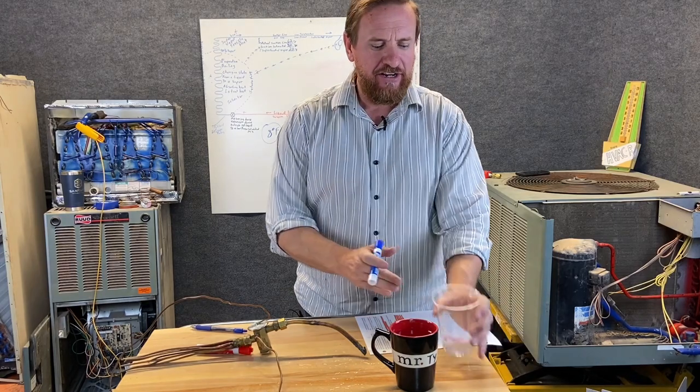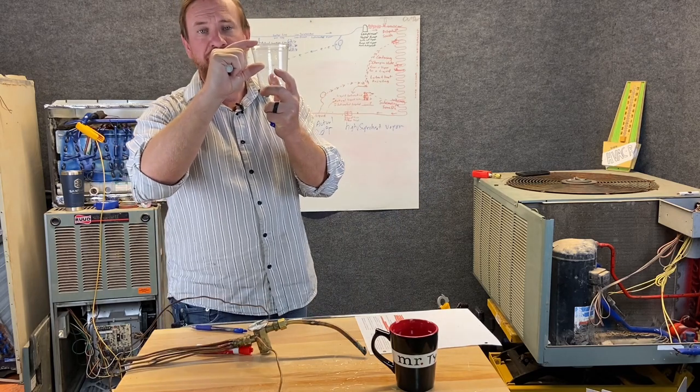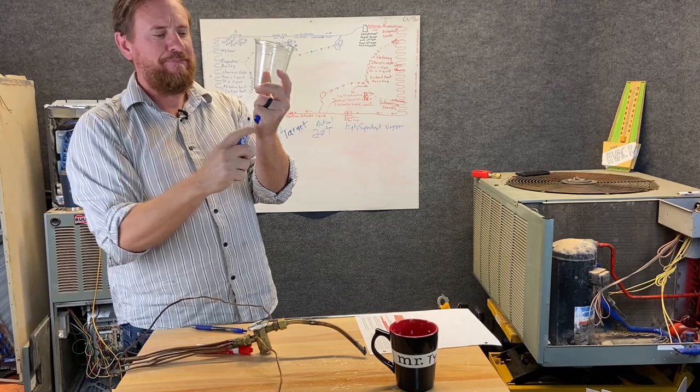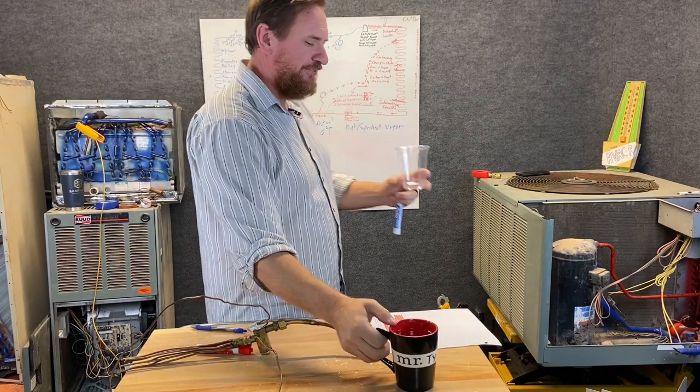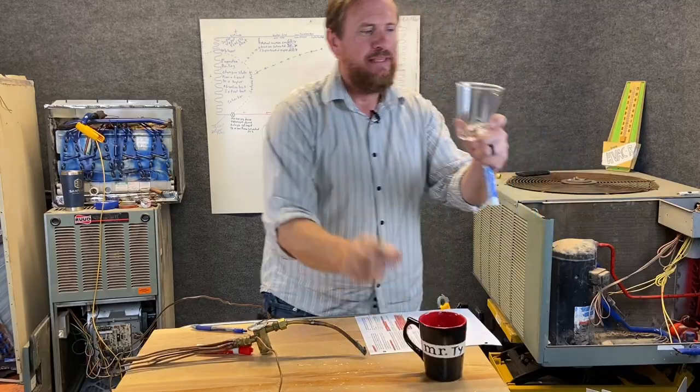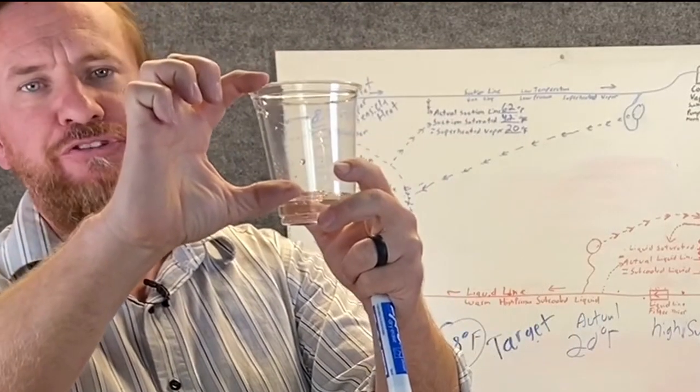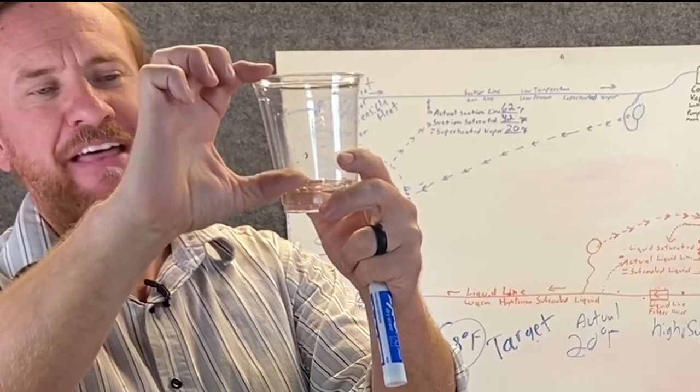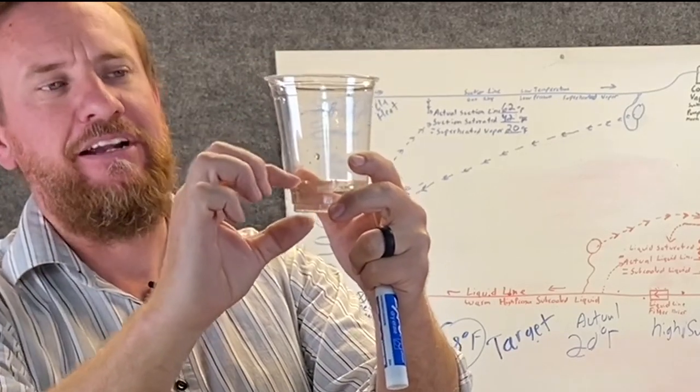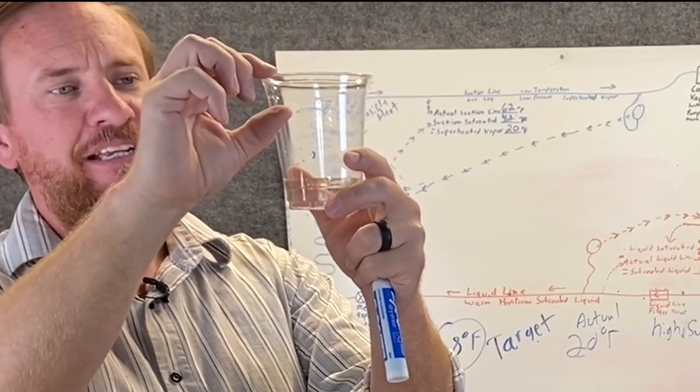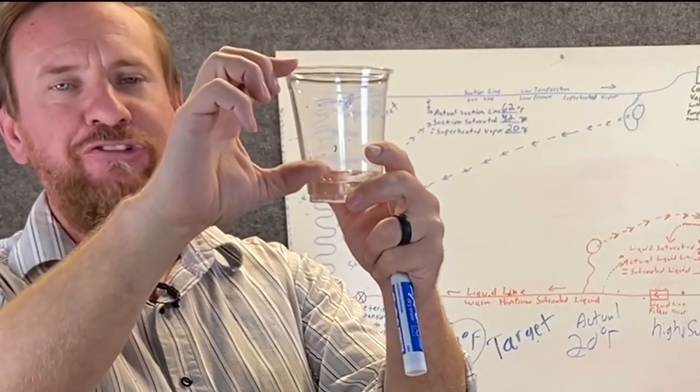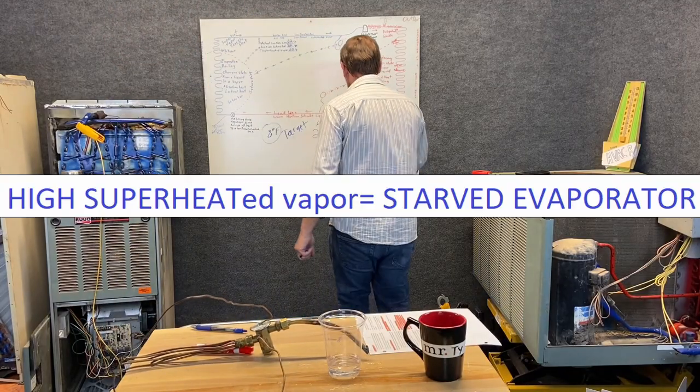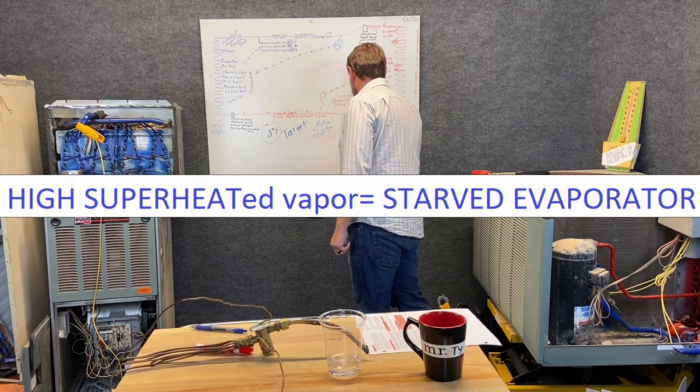High superheated vapor. So let's take a look on our cup idea again. Let's say we're talking about vapor. Let's say I want eight degrees of superheated vapor. But when we do the measurements, I have 20 degrees of superheated vapor. So I can only see the vapor and I want this much vapor, but I have that much vapor. That means I don't have enough liquid in here. So I want eight degrees of superheat, but I have 20 degrees of superheat. I have high superheated vapor. That means have a starved evaporator. High superheated vapor equals a starved evaporator.